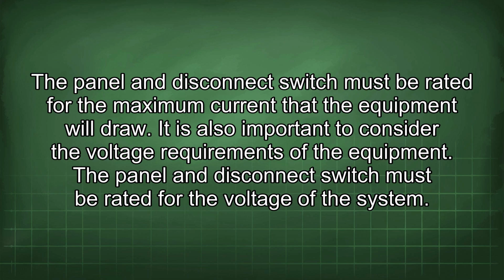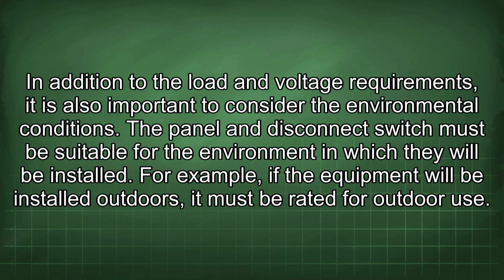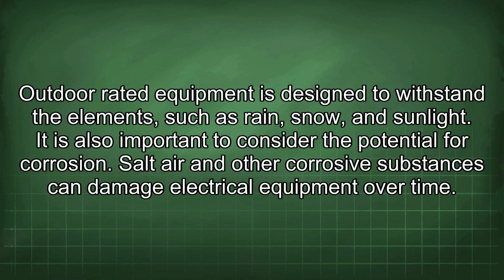The panel and disconnect switch must be rated for the maximum current that the equipment will draw. It is also important to consider the voltage requirements of the equipment. The panel and disconnect switch must be rated for the voltage of the system. In addition to the load and voltage requirements, it is also important to consider the environmental conditions. The panel and disconnect switch must be suitable for the environment in which they will be installed. For example, if the equipment will be installed outdoors, it must be rated for outdoor use. Outdoor rated equipment is designed to withstand the elements such as rain, snow, and sunlight.